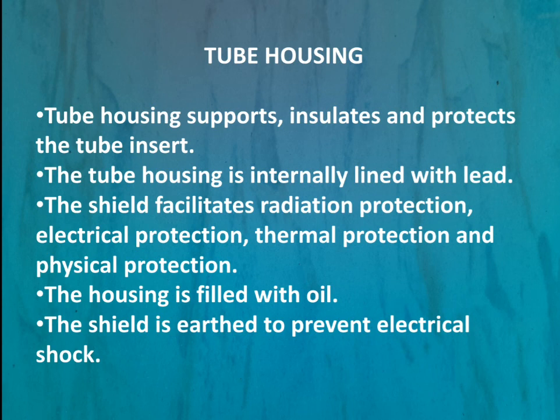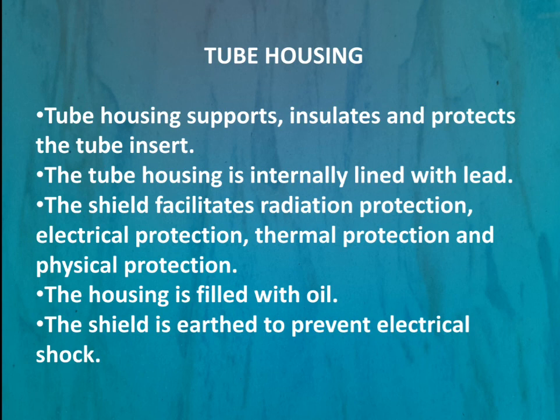Lead lining prevents the leakage of radiation in undesired directions. The housing provides radiation protection, electrical protection, thermal protection, and physical protection. The housing is filled with coolant oil or insulating oil, which acts as both a coolant and electrical insulator. The tube housing is also earthed in order to prevent electrical shocks.